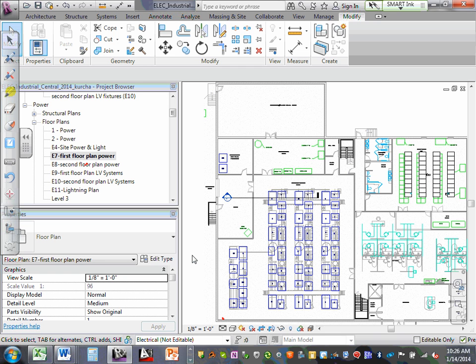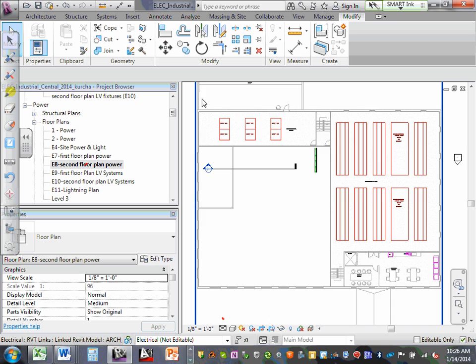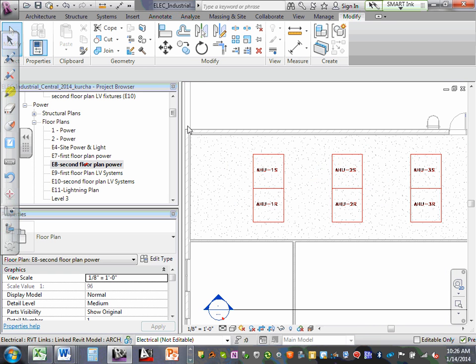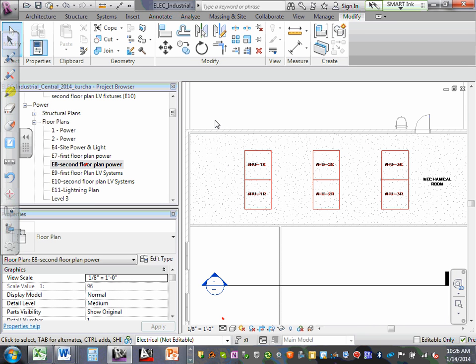And again, we go back to the air handling unit, where we have the smoke detector on the supply side. When that detector goes into alarm, we also have to shut that unit down. How are we going to do that? Well, we'll do a relay. So once that detector goes into alarm, the control panel says, okay, your software now, I have to tell that relay module to change state, and it does, and it opens the contactor that serves that supply fan and shuts it down.